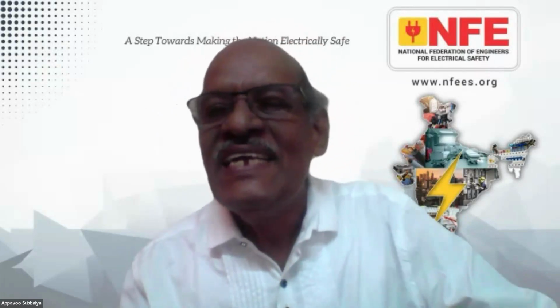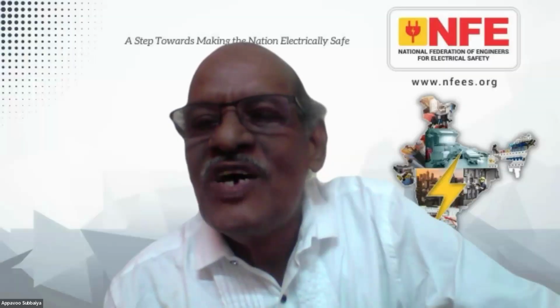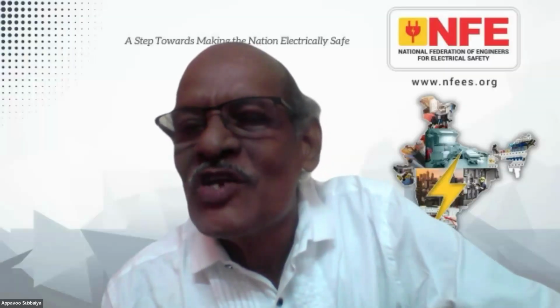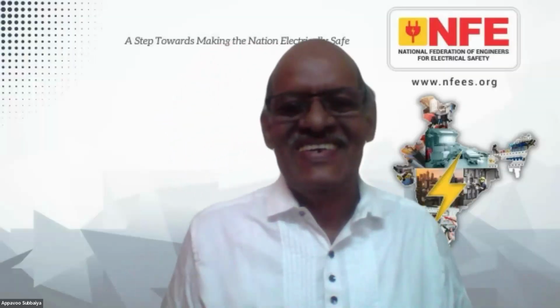As per CEA, yes sir, it is compulsory to use FRLS wire. Or actually, for point wiring, 1.5 square mm wire or 1 square mm is used. For any building wiring, minimum cross section of the wiring should be 1.5 square mm. That is clearly specified in IS 732.